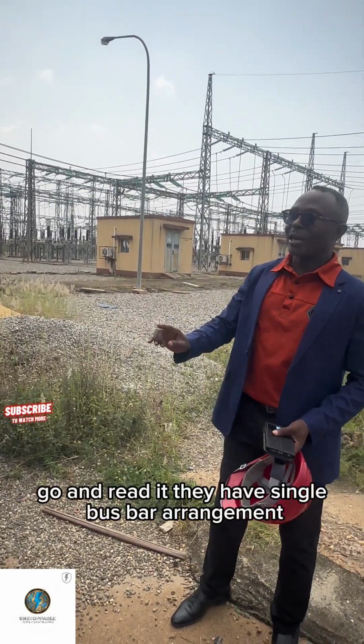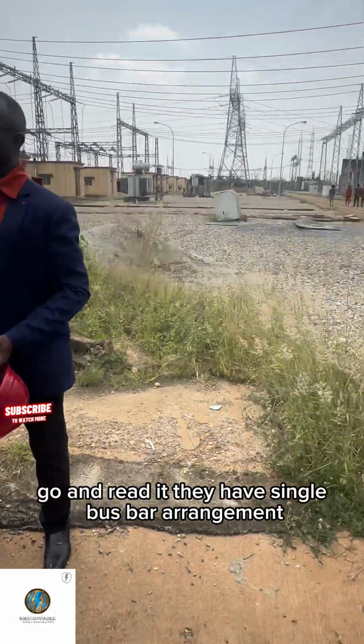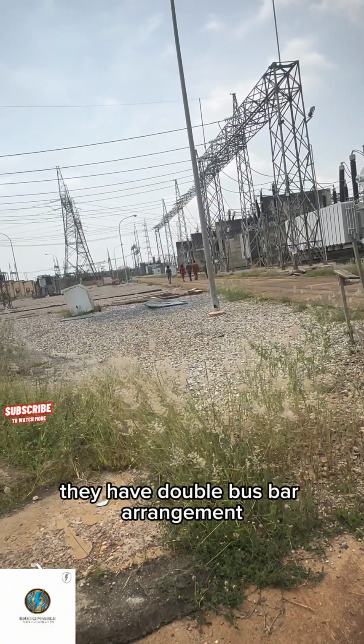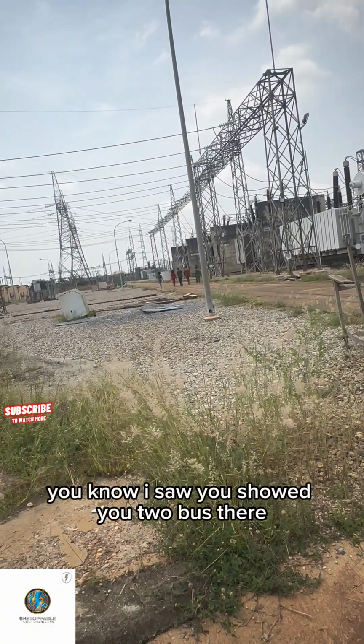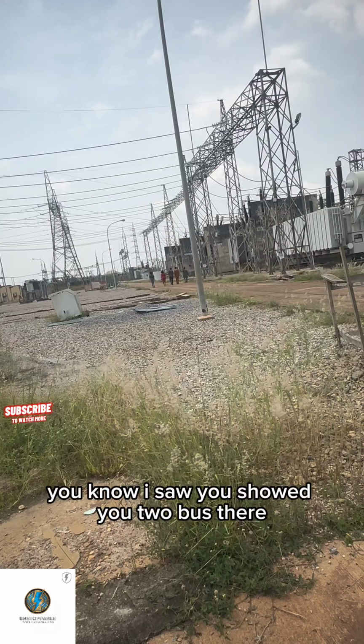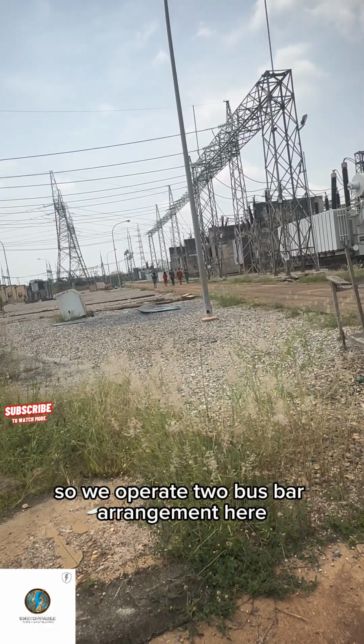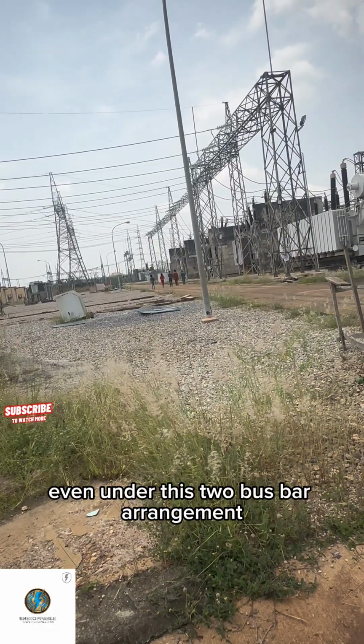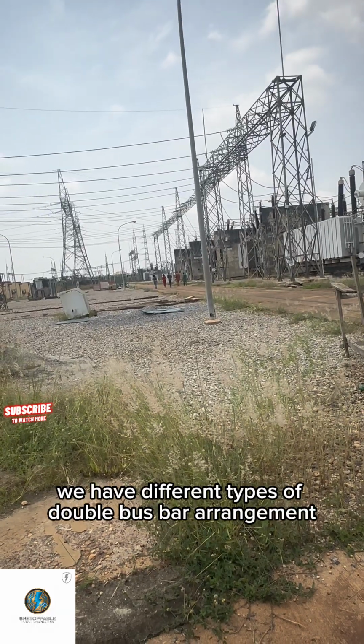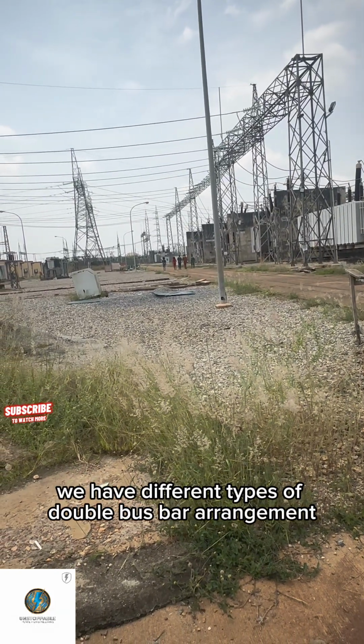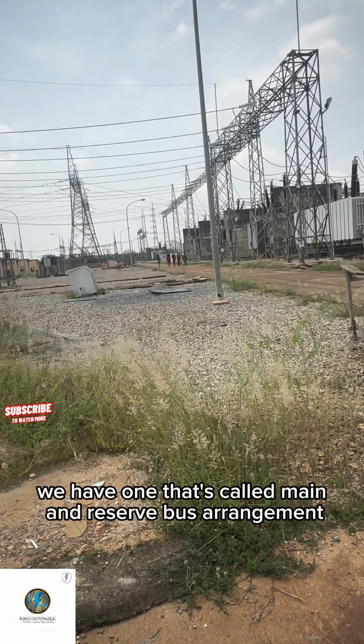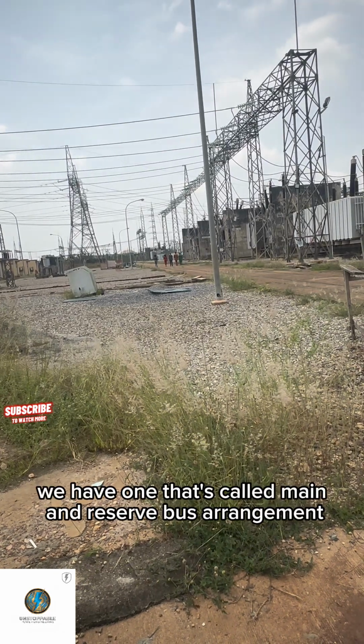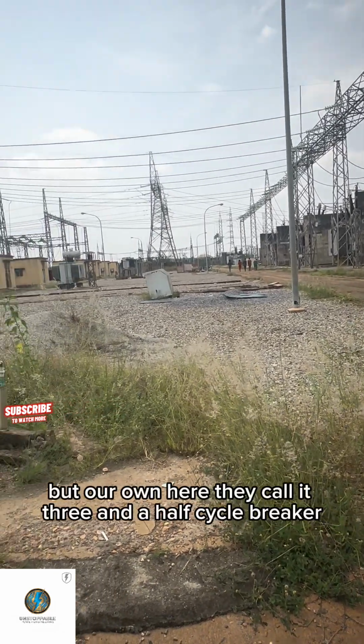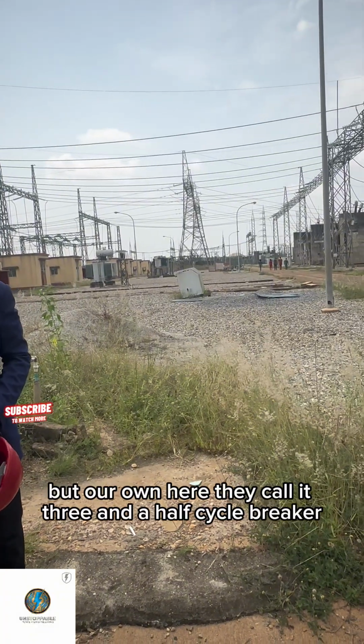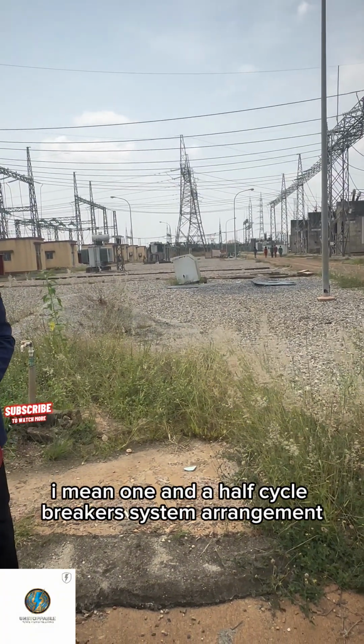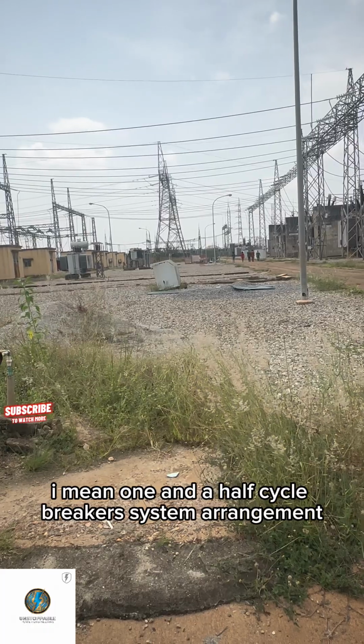Go and read it. They have single bus bar arrangement. They have double bus bar arrangement. I showed you two buses, so we operate two bus bar arrangements here. Even under these, we have different types of double bus bar arrangements. We have one called main and reserve bus arrangement. But our own here, they call it 1.5 circuit breaker system arrangement.